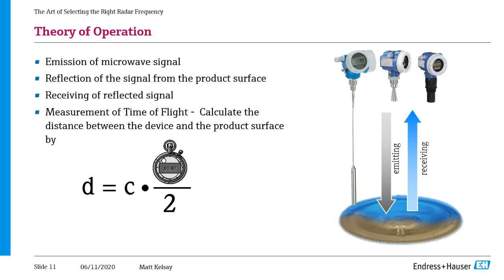So the difference between a radar and an ultrasonic here is the type of signal that gets sent out. So a radar is an electromagnetic wave, whereas an ultrasonic is actually a mechanical sound wave. So really the only difference in this equation that you see here is the C. For a radar device, that C is the speed of light, as the radar signal travels through air. Whereas for an ultrasonic, it's the speed of sound that the signal travels through air. Go on to the next.